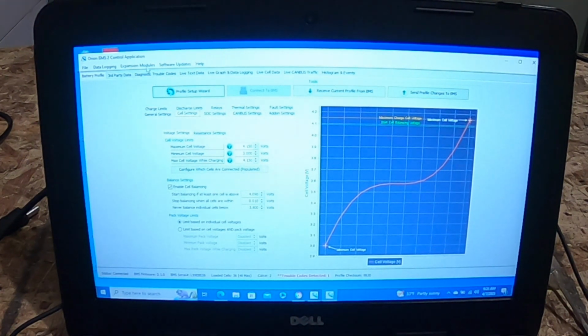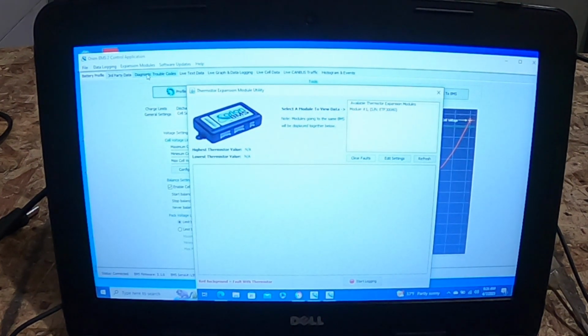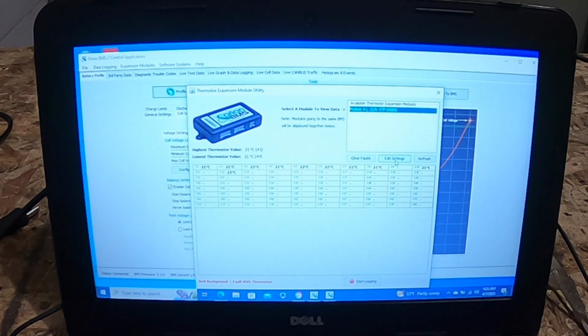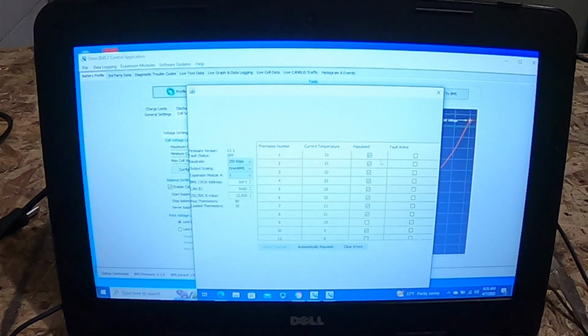The other thing is my expansion module, my Orion BMS. This is communicating over CAN bus 2, so I had to change the baud rate. Here's module 1, and if I edit my settings, I can see all my settings here, like thermistor 1's current temperature at 21 degrees centigrade.